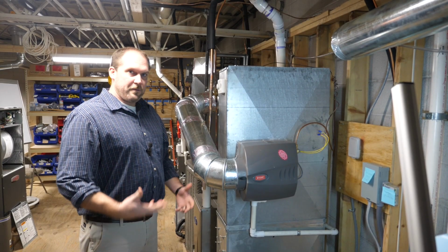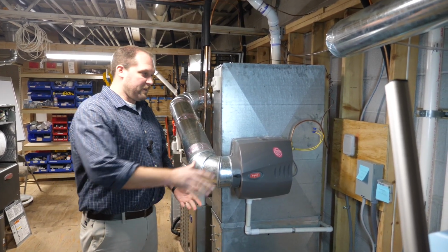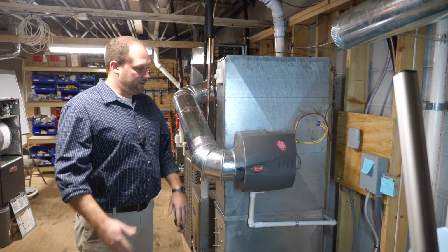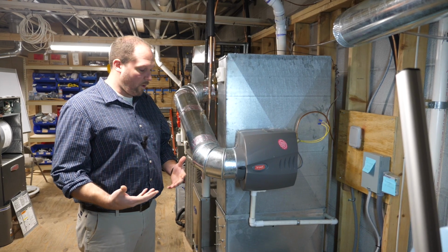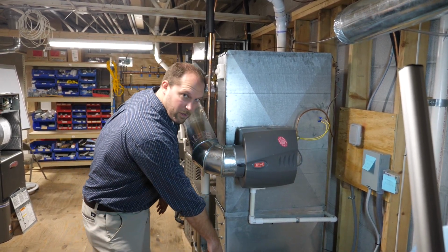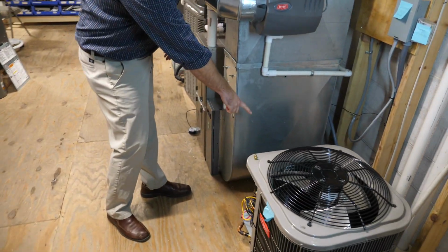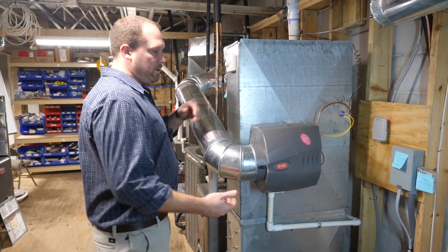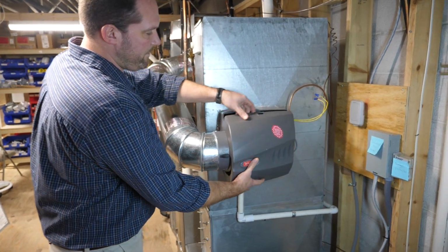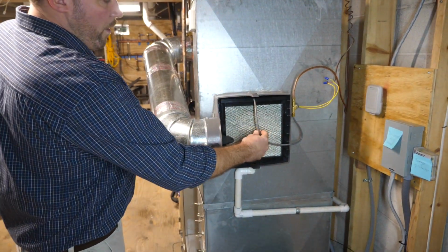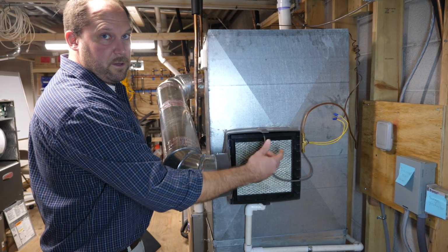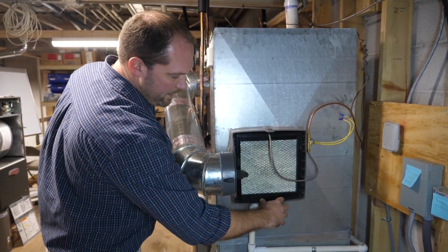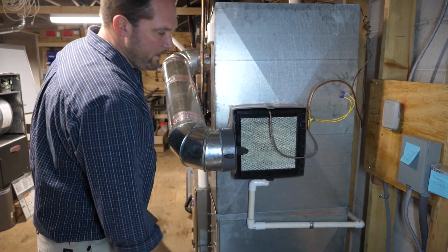are. All right, for those who aren't aware, this is what a typical humidifier looks like. So the common areas that you would notice water would be right below it, right there on the floor. Usually that's a common area that you'd see water, which could be due to, I'll take this cover off, the water pressure going through this tube. It could be too great to where it hits the back part of the humidifier and starts to drain down here and then onto the floor.